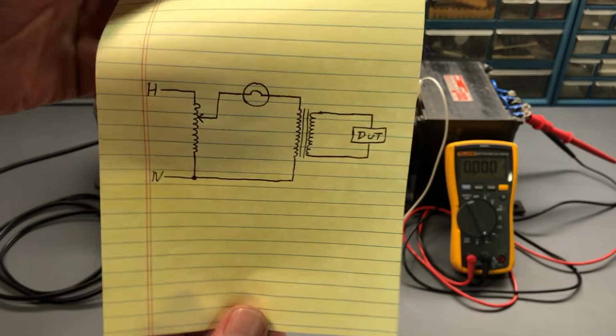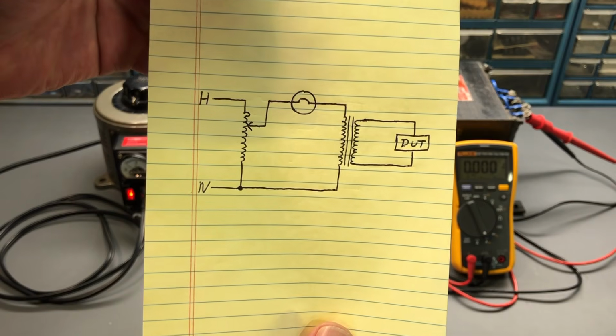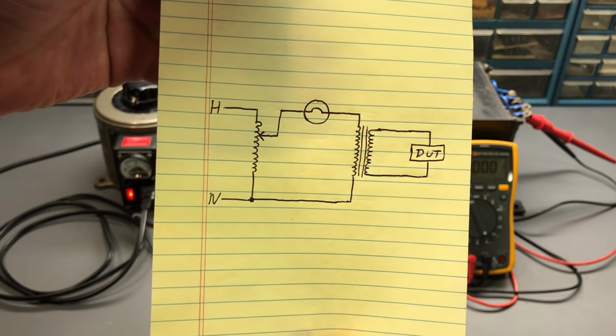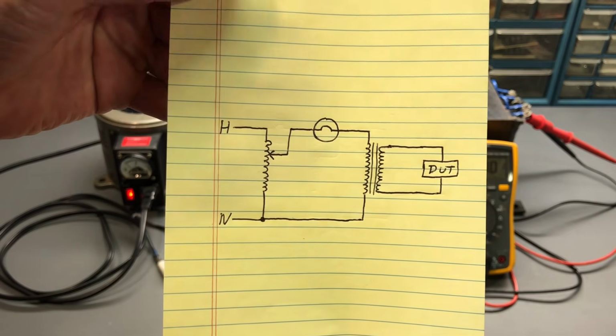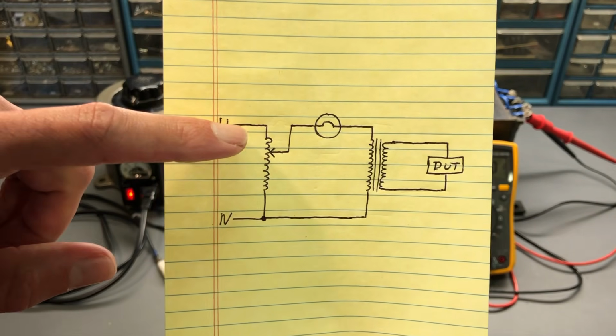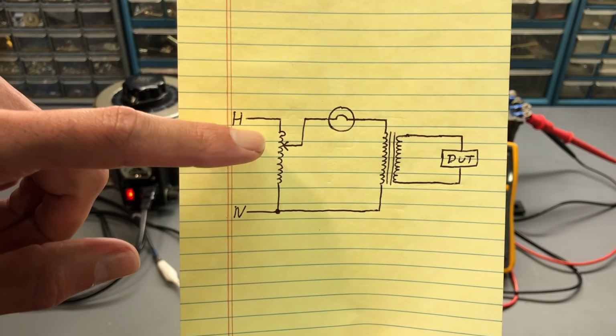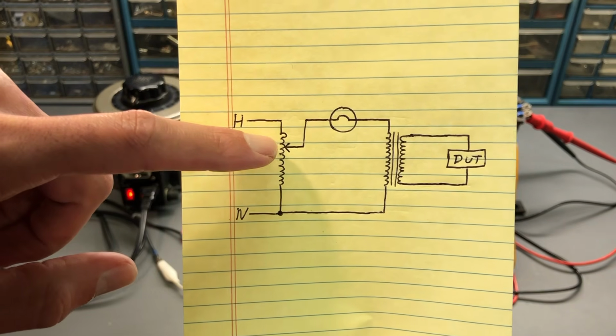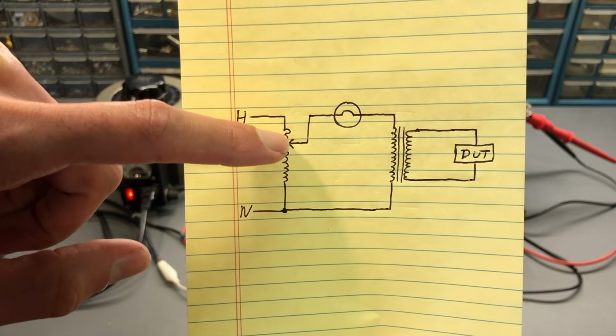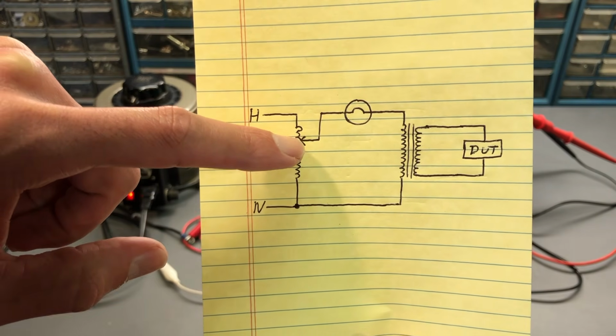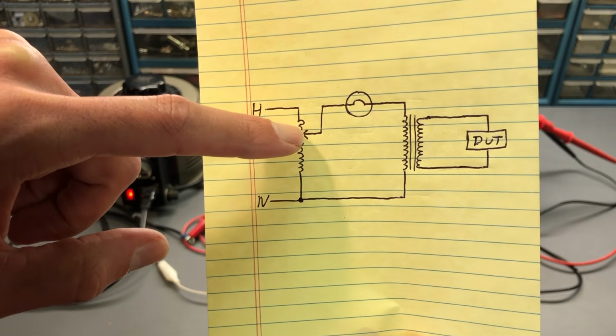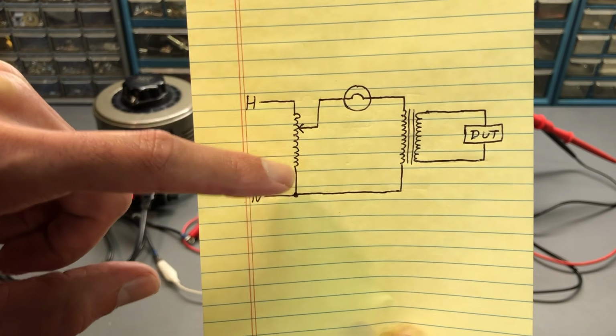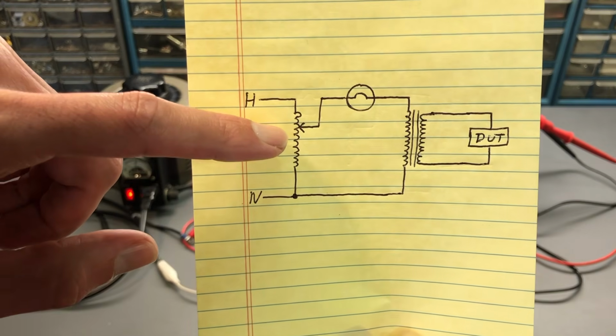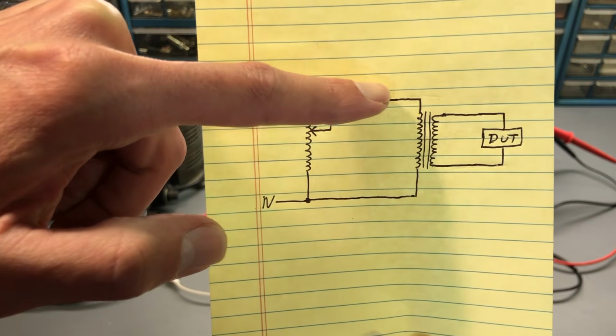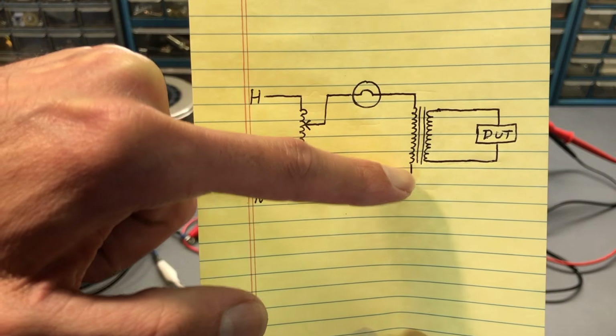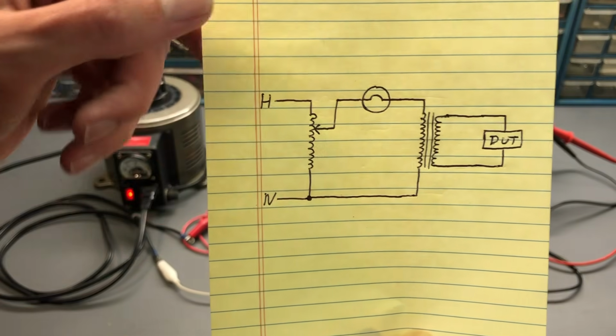So here's the schematic of that setup. You can see the DUT, device under test. That is the digital multimeter. And you can see over here the Variac, the AC hot and neutral line coming in. The movable tap within the Variac right here selects the winding that we want for the voltage. The further up this is, the more voltage you have. As this tap is brought down closer this direction, the less voltage comes out of the Variac. All right, so it comes through the incandescent bulb, through the primary of the isolation transformer, comes back around to the neutral.